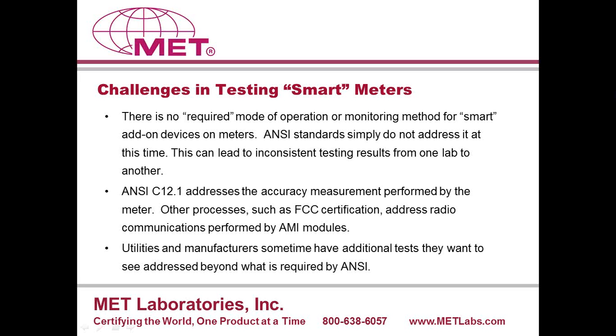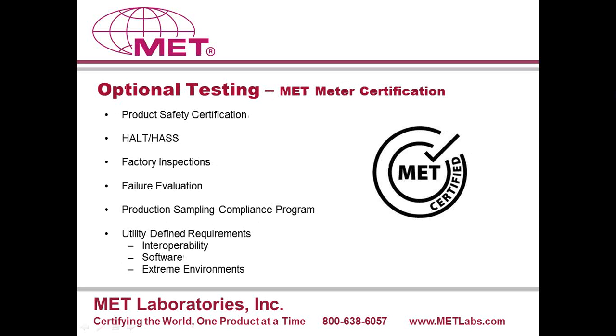Again, with the utilities, we perform side-by-side testing. There are transient tests that are performed on the meters, and quick transients and dropouts that are not in the ANSI standard. But again, seeing some issues and reoccurring events in the field, many times some of these come to light, and you want to try to recreate that in the lab, and we can certainly help you out there. So some of the optional testing can be either tagged along with or even separate from a meter certification program. It doesn't necessarily have to be tied directly into the meter certification program, but you may want to get into some other areas, such as product safety certification and product listing.